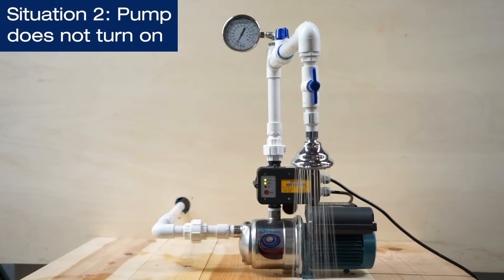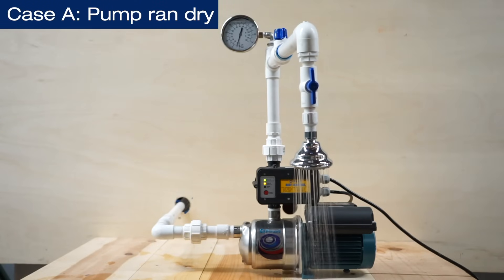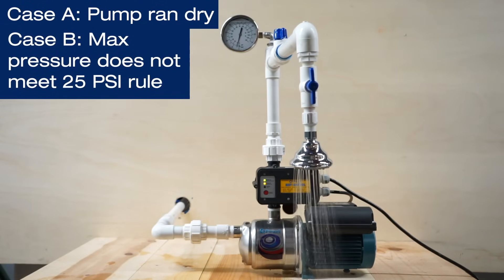There are a couple of reasons why the pump would be in failure mode. Either A, the pump ran dry, or B, the pump's maximum pressure does not meet the 25 psi rule.